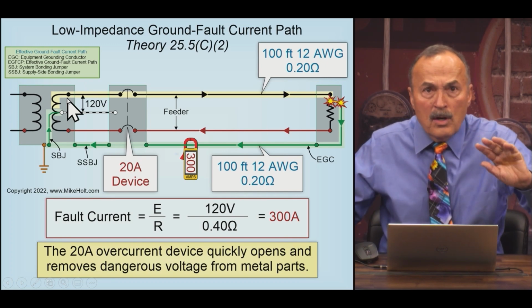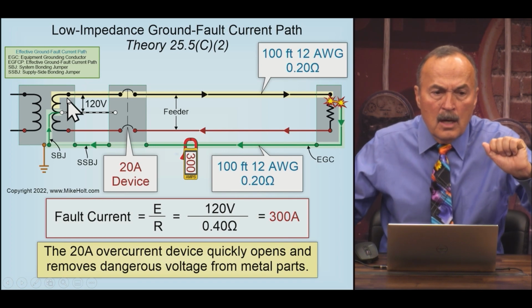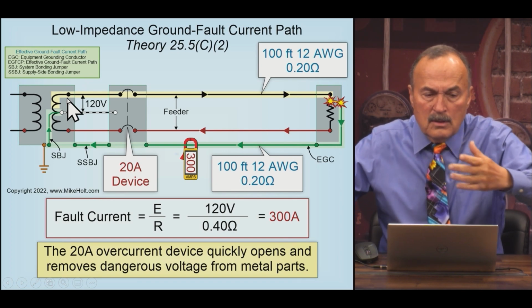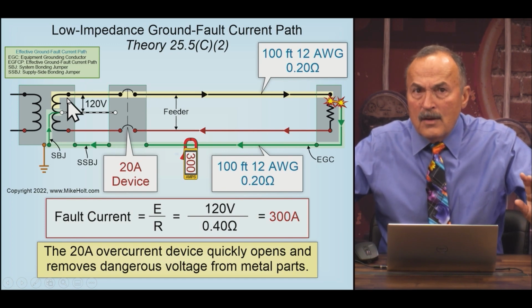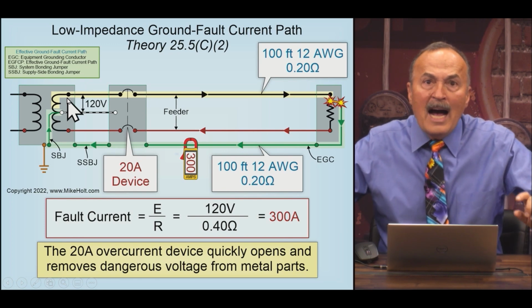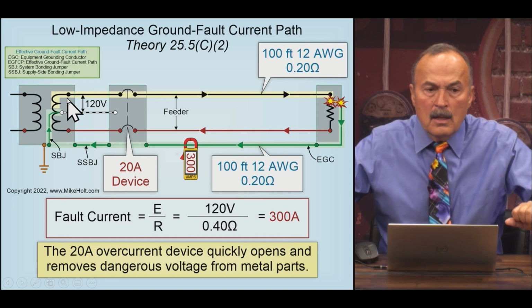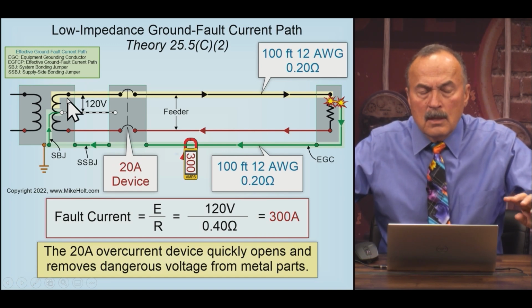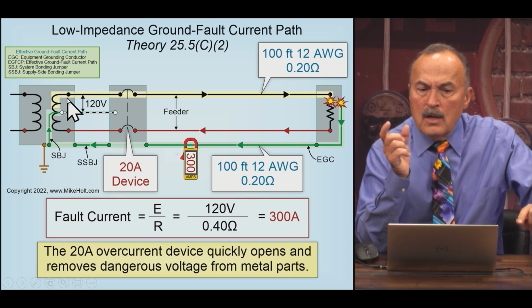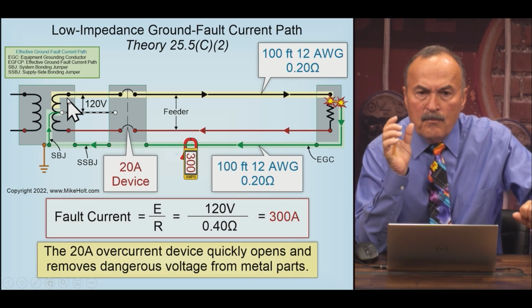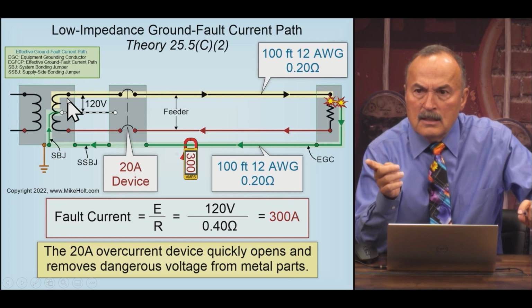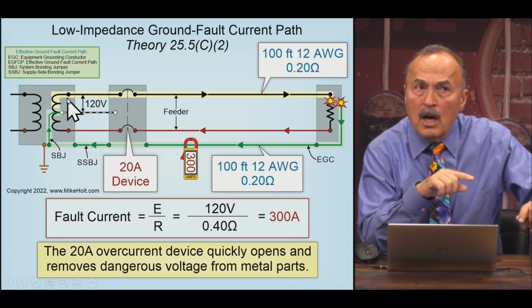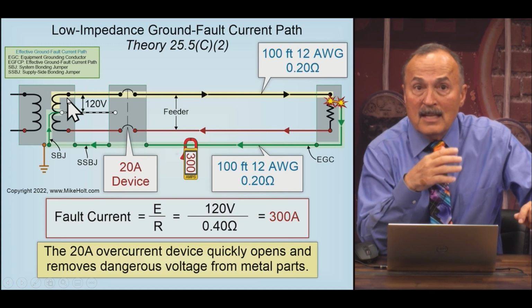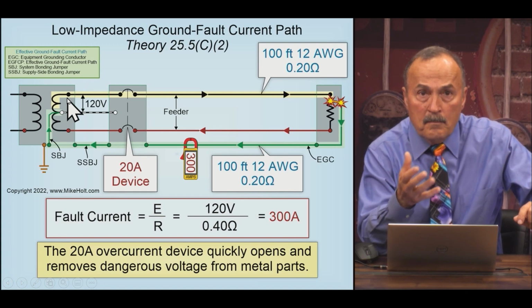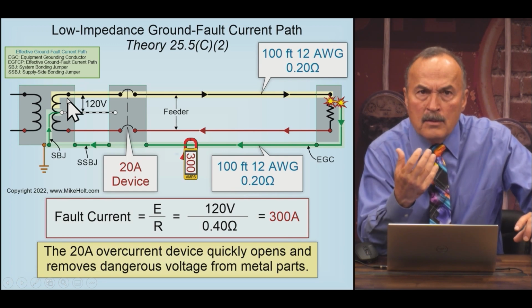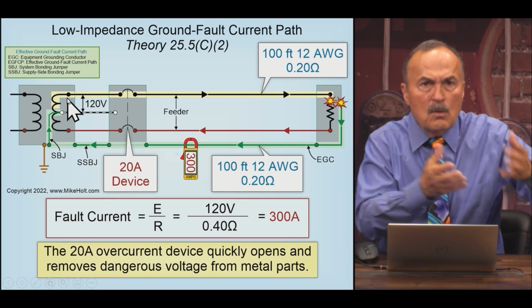Now, there are some code sections in here, Mario. There's a section, and I'll just tell you because I don't want you to have to scramble to know: 250.4(A)(5) in the National Electrical Code. I think it's 5. I think it might be 4. The one that I'm looking for, Mario, about facilitating the opening of the protective device, and there's a definition in Article 100. It's talking about the effective ground-fault current path. So now this is another name that you don't have to worry about right now. Just want to kind of put it in context.